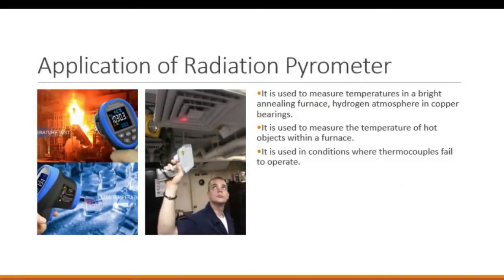Application of radiation pyrometer. As you can see, the image shows a Fluke radiation pyrometer and infrared thermometer. These are the applications of radiation pyrometer. It is used to measure temperature in a bright annealing furnace, hydrogen atmosphere, in copper bearings. Second, it is used to measure the temperature of a hot object within a furnace. Third, it is used in conditions where a thermocouple fails to operate. Over to you, Shubham.